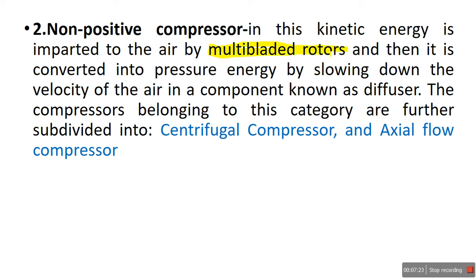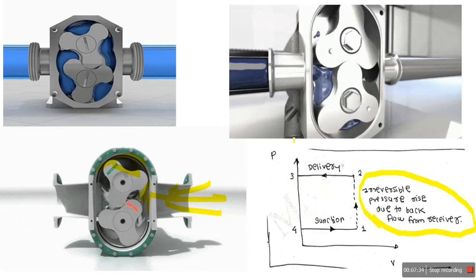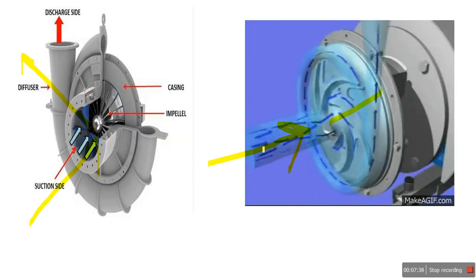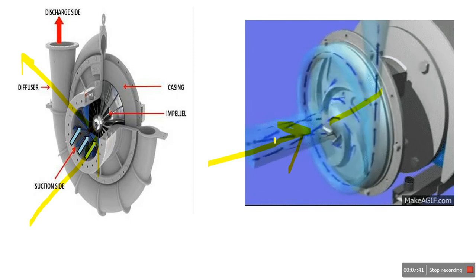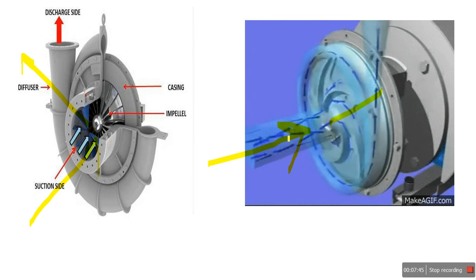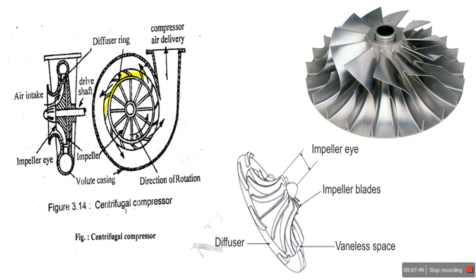In the centrifugal compressor the impeller acts as a multi-bladed rotor, and the kinetic energy imparted to the air is then converted to pressure energy by slowing it down. Initially the impeller imparts kinetic energy and also increases pressure energy. As the air moves into the diffuser, the diffuser reduces kinetic energy and gradually increases pressure energy. Further pressure rise is carried out in the volute casing — so in the impeller there is kinetic and pressure increase; in the diffuser kinetic energy reduces and pressure rises; and the final pressure rise occurs in the volute casing.